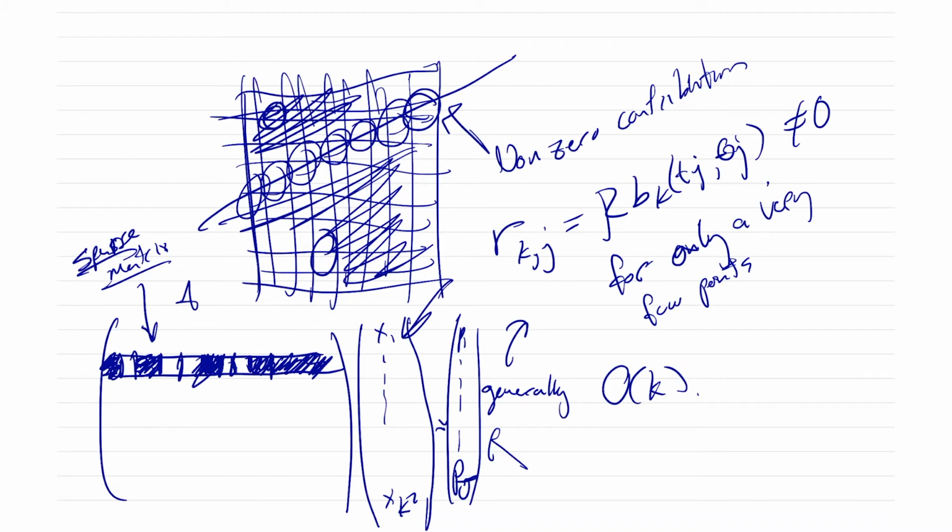And there are a lot of variables to pick out. So you'll notice that for the method that used filtered back projection, we didn't actually have to define what our pixels were, because the ultimate result we got was a function, and we can evaluate it at any pixels that we feel like. But in this case, since it's an algebraic reconstruction technique, we actually have to define exactly how many pixels we have, and then try to build off of that. So this builds in challenges of its own, and it gives you a bunch of parameters to play with, which can be good, but it's easy to make a system that doesn't have any actual solution.